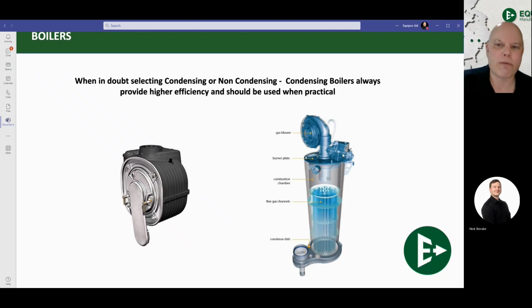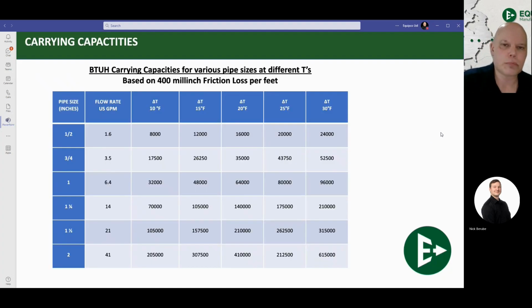These are the two that you're likely going to find on job sites and in most boilers here in this existing marketplace. Okay, so we talked about condensing versus non-condensing boilers. I talked to you about standard condensing heat exchangers. Now I want to talk to you about pipe size. Pipe size is extremely important, and we want to make sure that we get it right. Because if we put our pipe too small, we're not going to carry the heat out of the system.